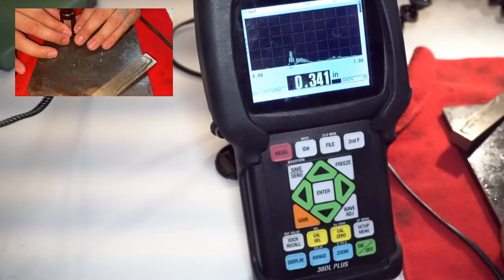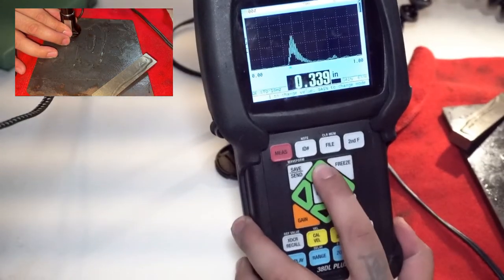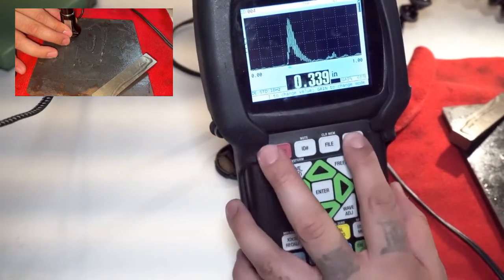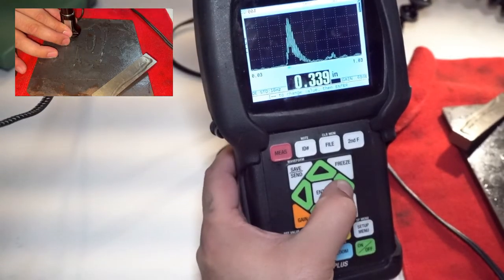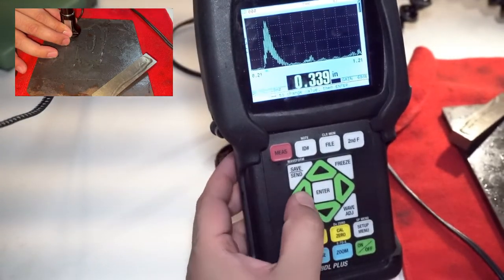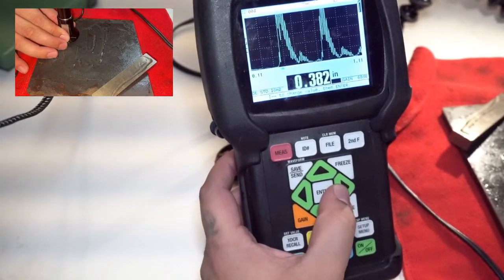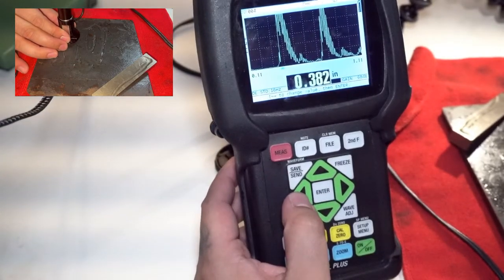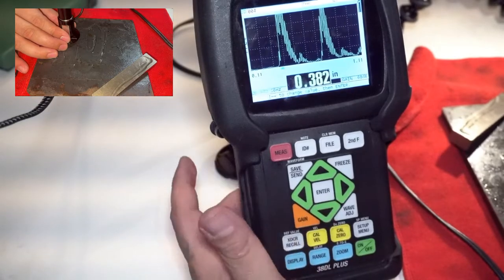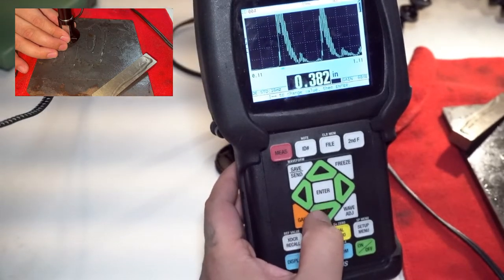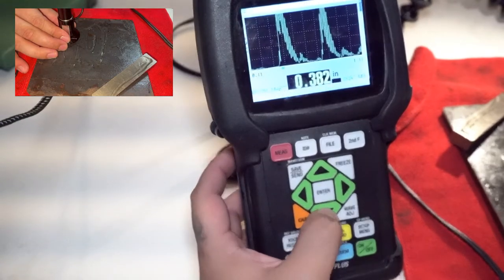We don't really see it. And crank up just a little gain just for demonstration purposes. And you see here it's gone. Now, if I was to go further off in time with the delay, you see no more back wall, secondary back wall echo, like I see it now. Now, these little signals here, as we talked about before, these are mode converted echoes. Anytime that you introduce sound at an angle other than zero, you're going to have refraction and of course, mode conversion. So we're going to have some shear waves.